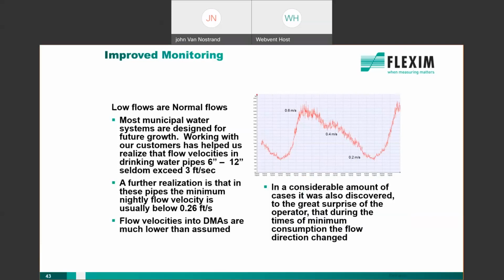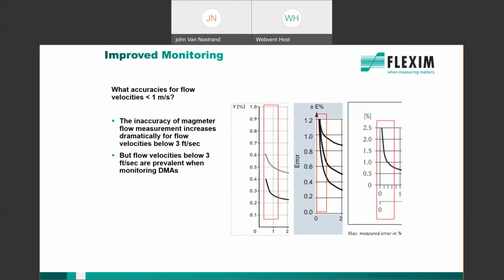So with low flows like this, it's nearly impossible for conventional meters to capture the movement of the water. So off-peak times, your meters could be far less accurate than you think they are. So below 3 feet per second, the Magmeter particularly drops off. I've talked about that a little bit before. Now you couple this with the lead and copper regulation, if you have alarm limits of below 15 parts per billion, that creates a whole new concern because you're putting corrosion inhibitors in the water, making your electrodes less sensitive than they should be. So that's a major concern as well.